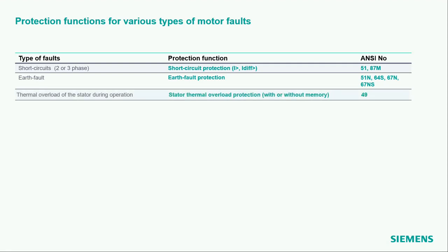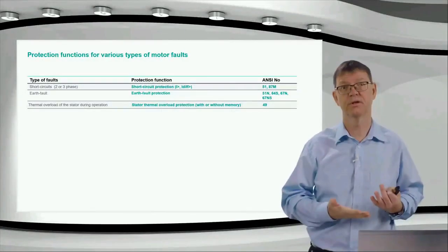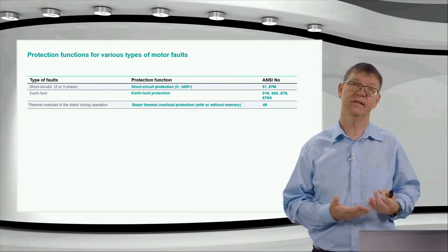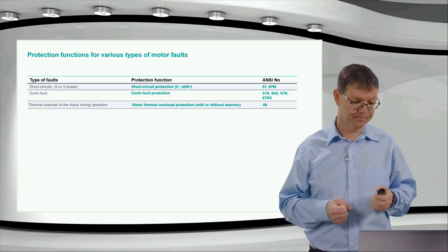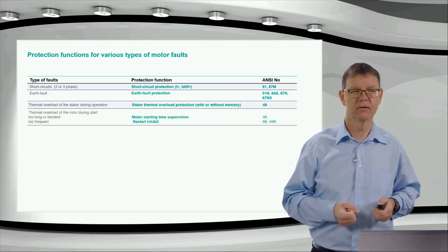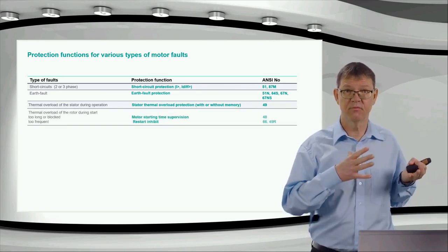Okay, we have a thermal overload of the stator. And this can happen during normal operation, so not during the startup. The startup is more stressing the rotor. During normal operation, if the current is too big, the load is too big over a longer time, then I can overload the stator. And therefore, we have a thermal stator overload protection function.